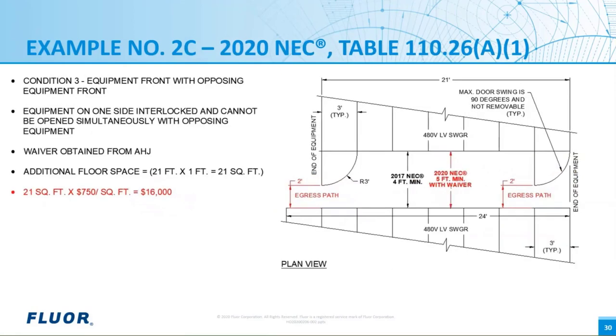Okay, here's an example of where special permission may be obtained from the authority having jurisdiction. This is a condition 3, similar to what we looked at before. But in this solution, the AHJ has provided special permission, a waiver, because safe switching procedures are documented and only qualified persons are able to access the equipment. The AHJ would need to invoke NEC section 90.4 and issue a written waiver for this to be acceptable.